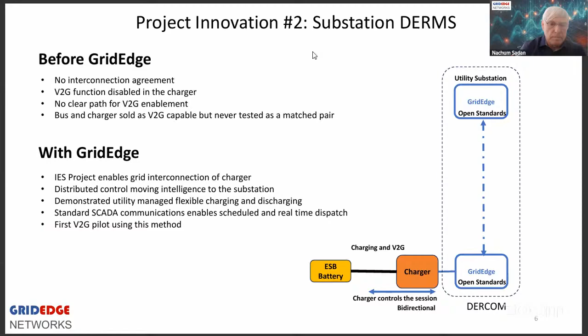What is innovative in this approach, again being the first V2G pilot using this method, is bringing side flexibility closer to the edge. The use of a standard SCADA interface at the substation enables the utility to send schedules and demand dispatch signals on a secure channel and real-time response to grid constraints. What we demonstrated were charger reactions to simulated grid constraints and setting of charging and discharging schedules.